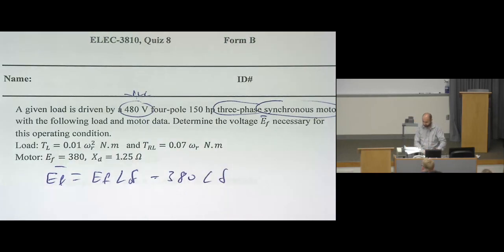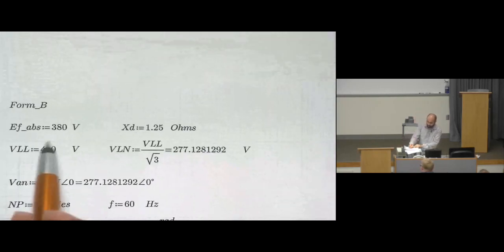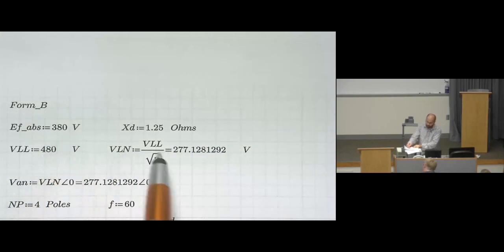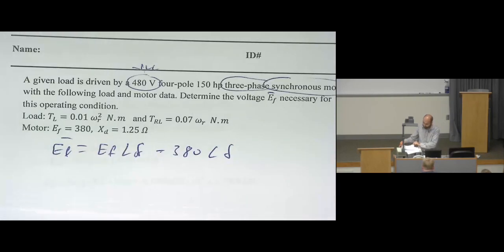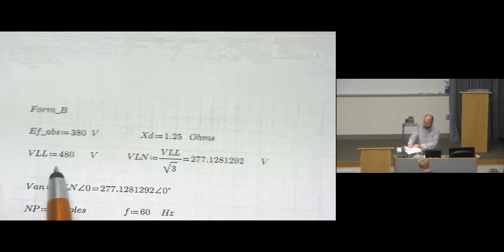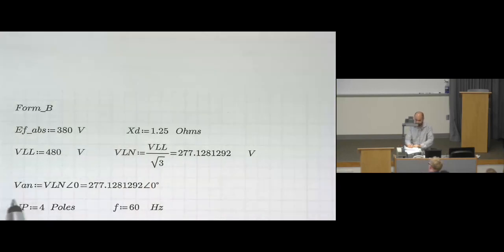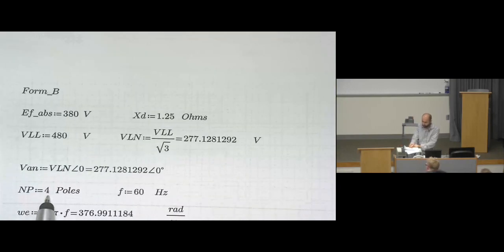Let's analyze what we have: the magnitude EF is 380, XD is 1.25, and we have V line-to-line, from which we can find V line-to-neutral and VAN. We also know the number of poles is 4 and the frequency is 60 hertz.